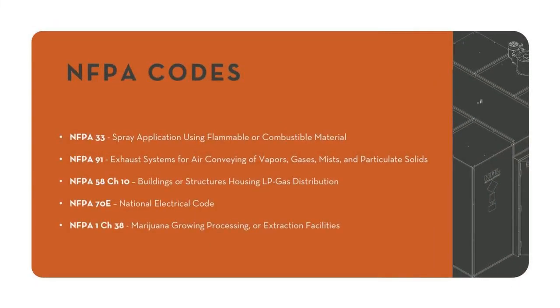So the classifications. Here I've pointed out a number of NFPA codes that are very important and applicable to extraction facilities and rooms. I'm just going to go through a couple of them and point out some key factors that we've kept in mind in designing a room, and most companies would keep in mind in designing a room. In NFPA 33, there's some verbiage as to what sort of material these rooms can be made out of. They also mention not allowing the lower explosive limit to exceed 25%. So obviously the room has been designed to keep that below 25% by purging that air constantly, starting at 10%, so it doesn't build to that 25%. You'll see that 25% threshold in a lot of codes. So it's a very important one.